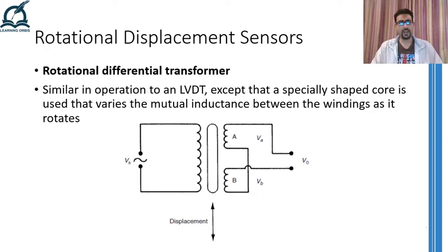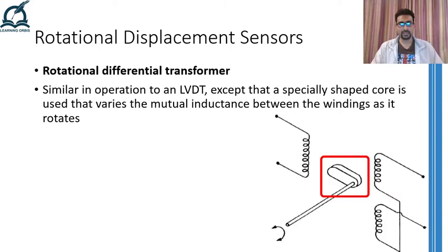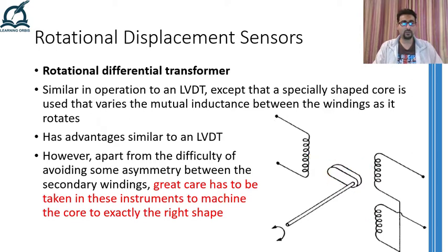The next rotational displacement sensor is a modification of a linear displacement sensor — the LVDT, or linear variable differential transformer. As discussed previously, the movement of the core between the primary and secondary sides dictates the voltage received at the secondary side. In the LVDT the core movement was linear. However, if this kind of core is rotated about an axis, that rotation affects the amount of voltage induced in both secondary coils. This is called a rotational differential transformer. In the shown position, the magnetic flux between primary and secondary coils is equal, giving no output on the secondary side. If the core is rotated clockwise, the flux linkage with the upper secondary coil increases while that with the lower secondary coil decreases, giving an increased voltage output with a positive phase.